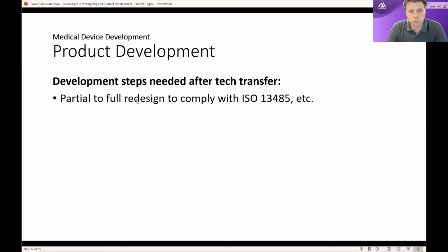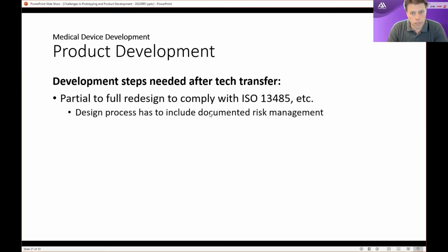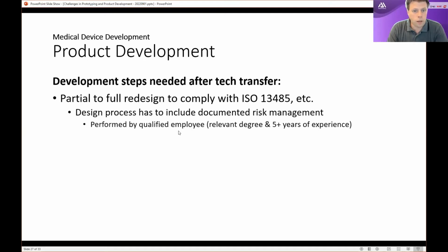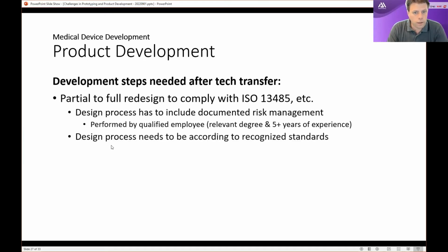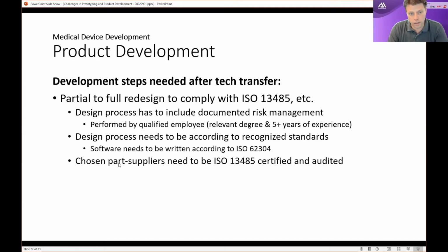You need to partially to fully redesign it to comply with the 13485. This means that you have to do documented risk management performed by a qualified employee. The design process needs to be according to recognized standards. The software needs to be written according to the standards. You need to do elements such as choosing part suppliers according to your standards.